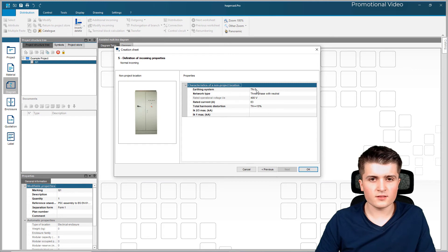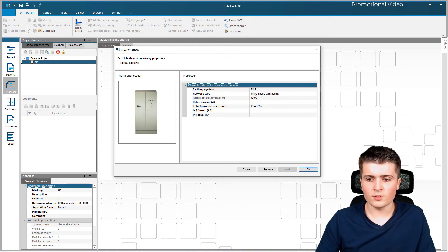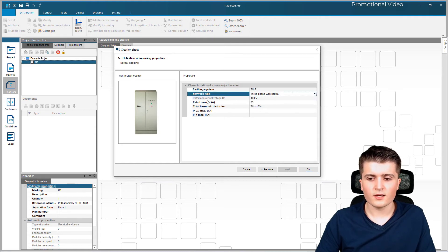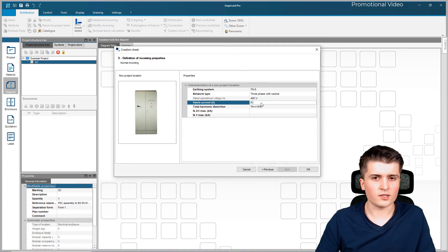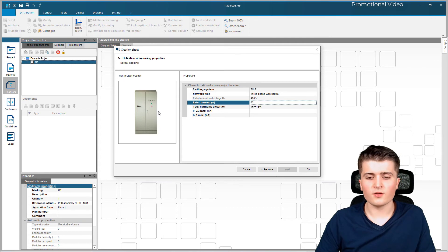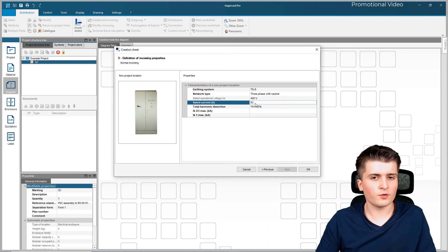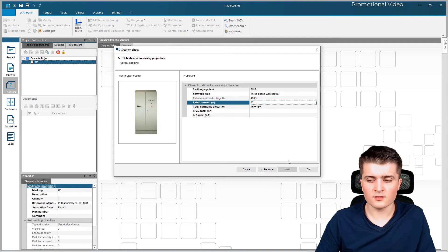I now have to specify the non-project location - the incoming. First of all the earthing system: I will use TN-S, so we have neutral and protective earth separated. Then the network type: I will use three-phase with neutral, though you could also use single phase. The voltage is automatically set to 400 volts and the only thing I can change now is the rated current - in this case I stick to 63 amps. This might be a different value in your case, but for now just stick to your value. Then we click OK.